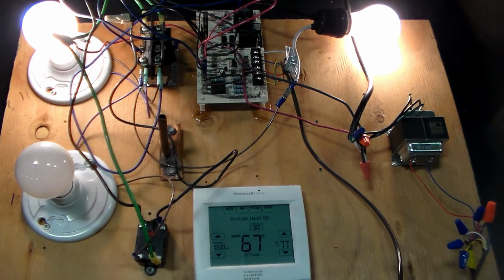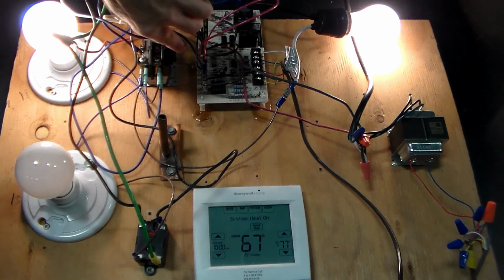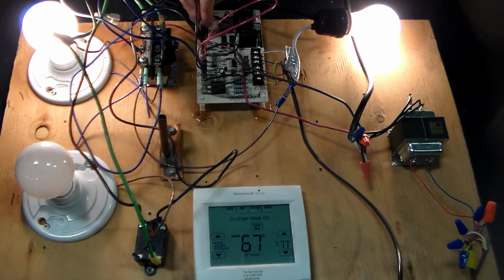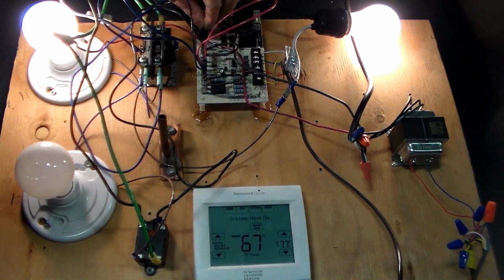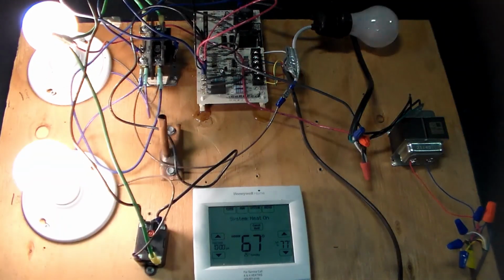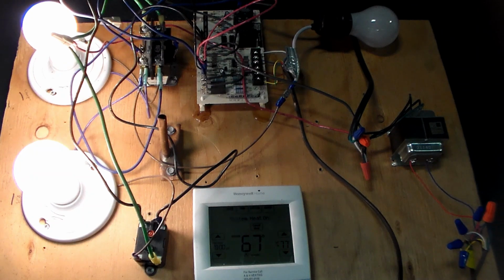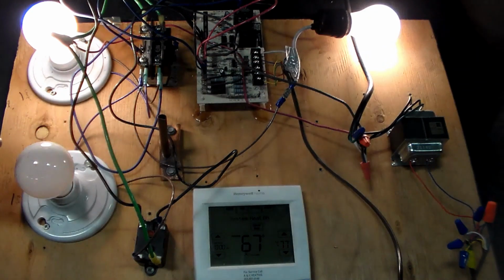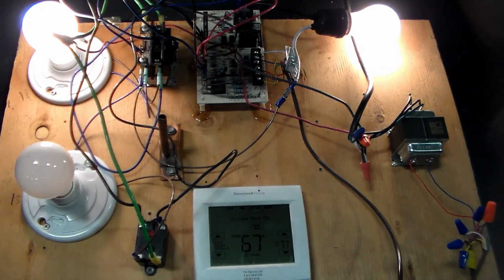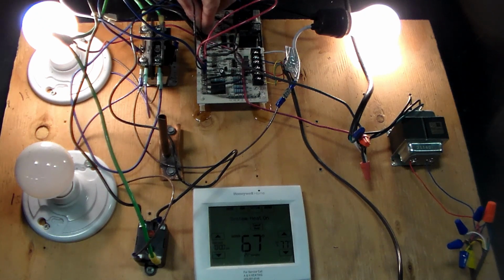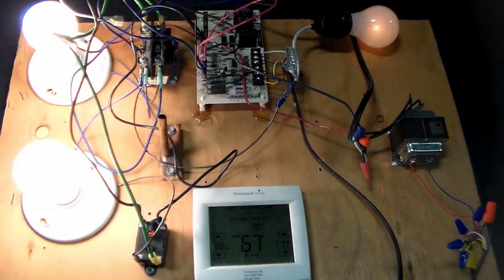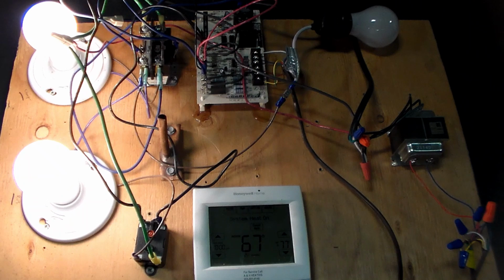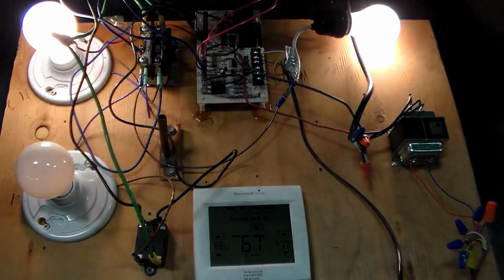When it goes into defrost, we first jump out our DF sensor, and then we take this jumper pin and jump it over here to these test terminals. And that should cause it, there we go, to go into defrost mode. So now it kicks on your reversing valve, switching it into cooling, and it turns off your condenser fan. You see how fast that kicked back out? If it's not actually frozen, it's going to kick back out after a while. But we can see that it cuts the condenser fan.